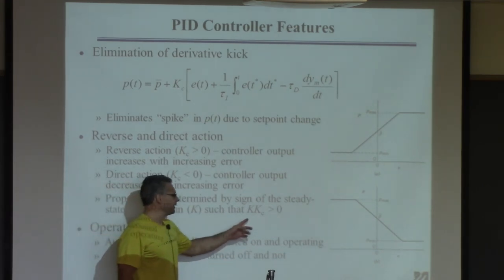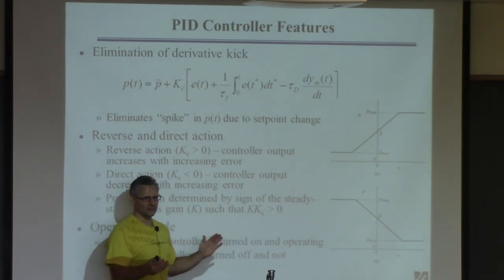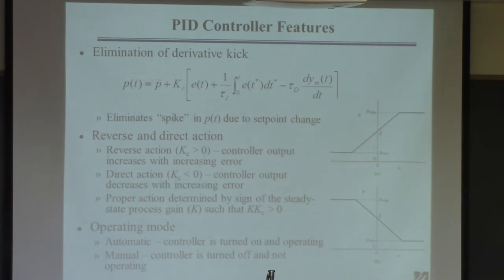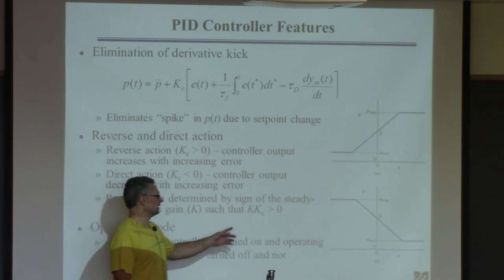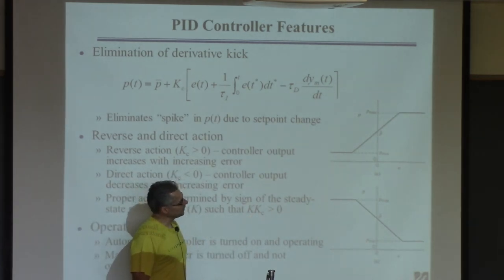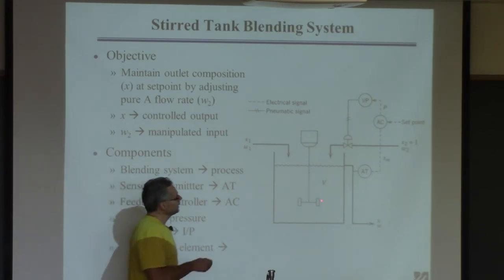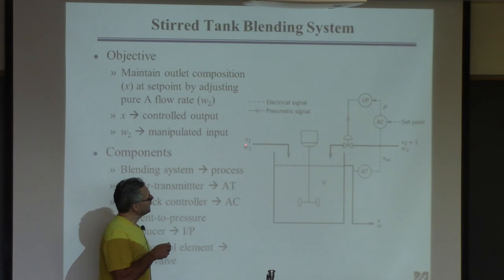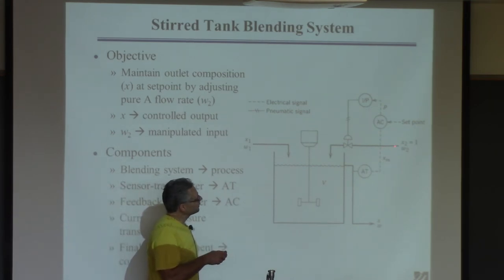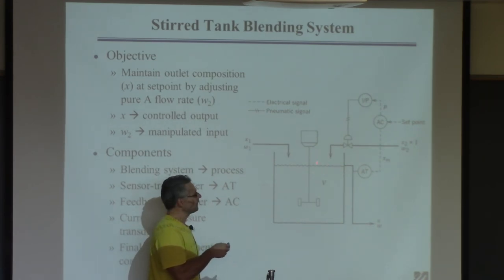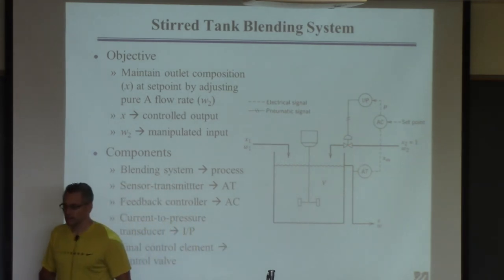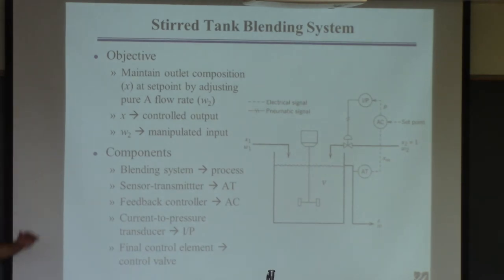If you use the wrong sign for the controller gain, the controller does the opposite of what it should. For example, if the outlet stream doesn't have enough component A and the controller has the wrong sign, it will reduce the flow of pure A further — making things worse — until the valve is fully closed. Any time in the lab your controller slowly moves to one extreme and stays there, there's a good chance the controller gain has the wrong sign.